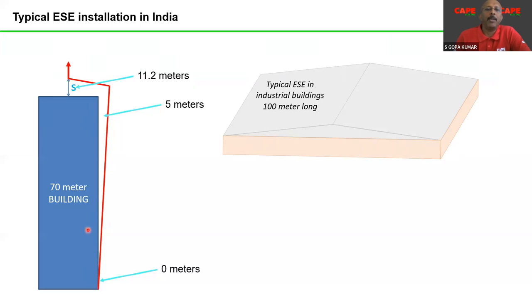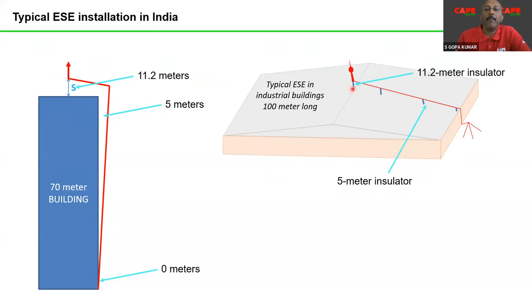In an industrial building hundreds of meters long, the distance is something like this. You have to have an insulator here, 11.2 meters, another insulator, probably 5 meters. So basically, the air terminal and the down conductor have to be kept 11.2 meters away from the building. This 70 square mm wire insulation, 1.1 kV insulation, has nothing to do with this 11.2 meters insulation. 11.2 meters insulation is a large insulation. The spark over voltage, or the voltage which is going to be created due to the surge impedance of the cable, is very high. This also means the lightning current flowing through the conductor to the down conductor can make a flashover up to a distance of 11.2 meters.